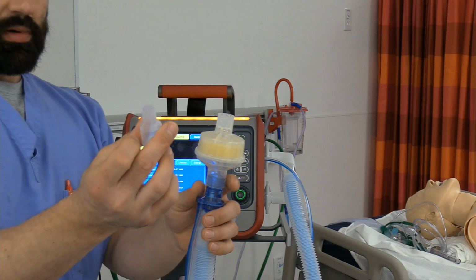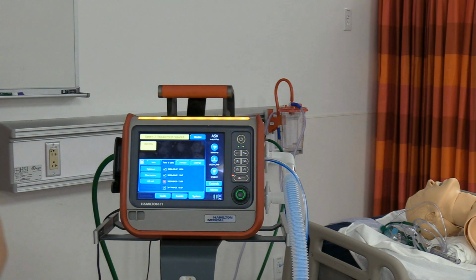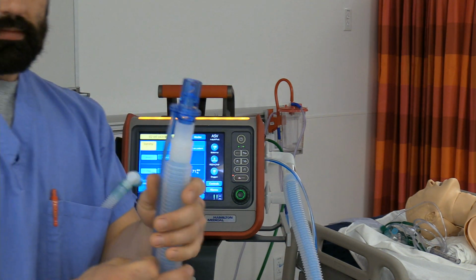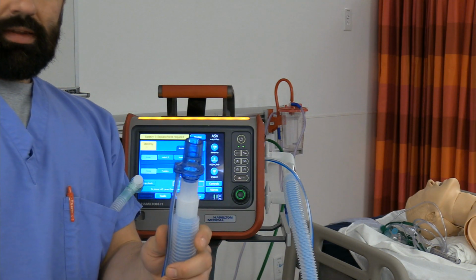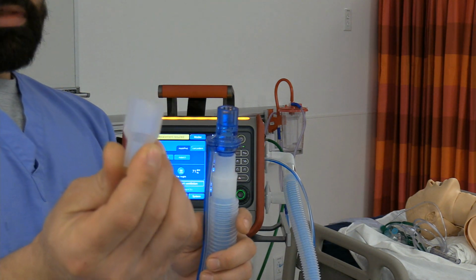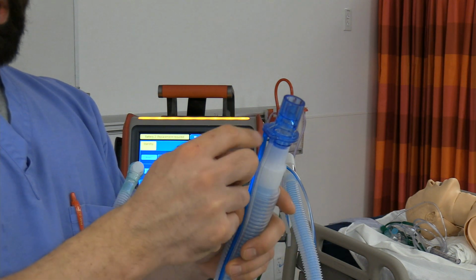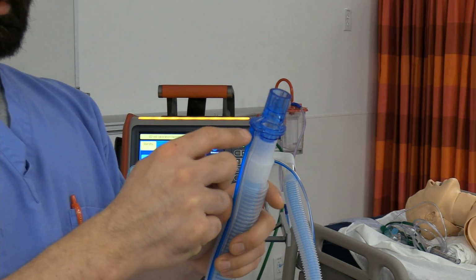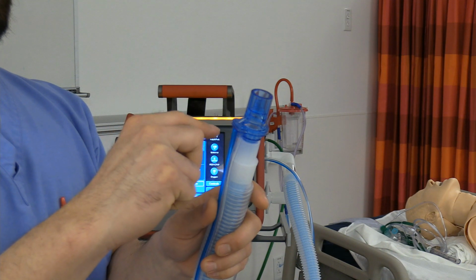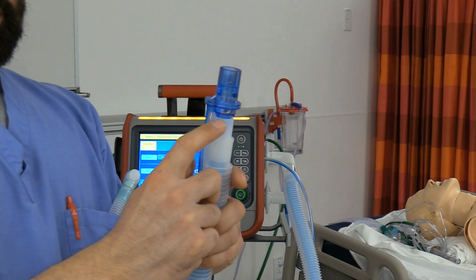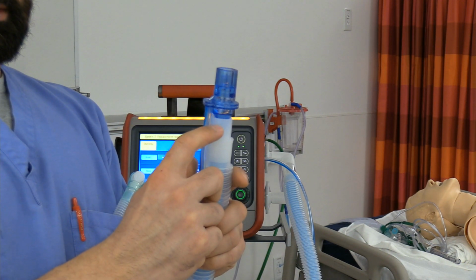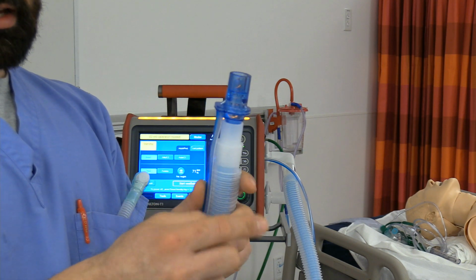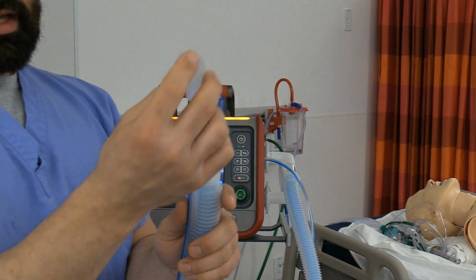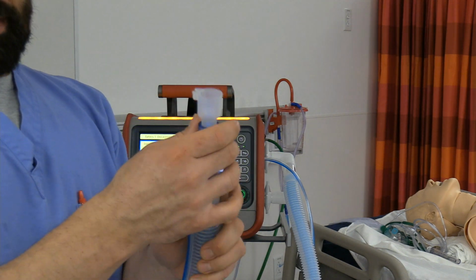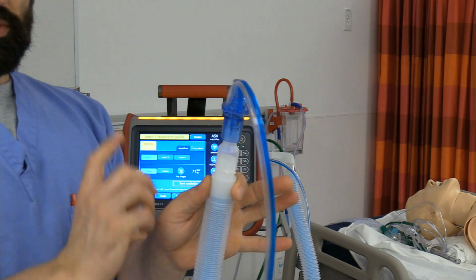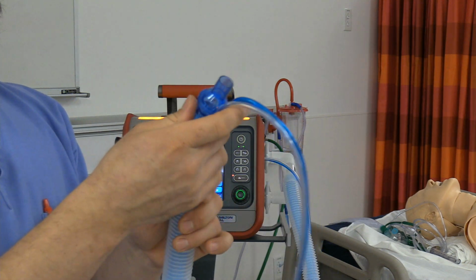You are going to need this particular clip. I'm going to remove my HME here real quick, although I probably don't absolutely have to. You're going to need this piece of plastic, because this piece of plastic that comes with that flow sensor, we're trying to calibrate and kind of zero out this flow sensor, and it's trying to mimic gas coming from the ventilator side as well as the patient side. So the way it's hooked up right now easily can mimic gas coming from the ventilator side, because it is. This piece allows us to put that on the top and flip this thing around when prompted to mimic air coming from the patient side of things.